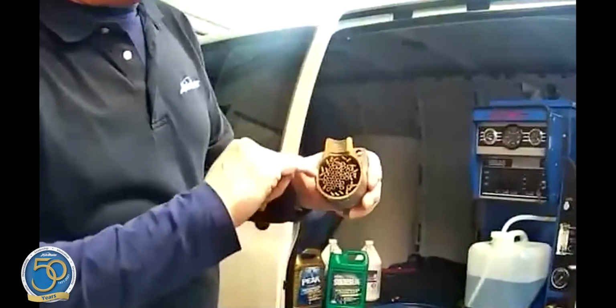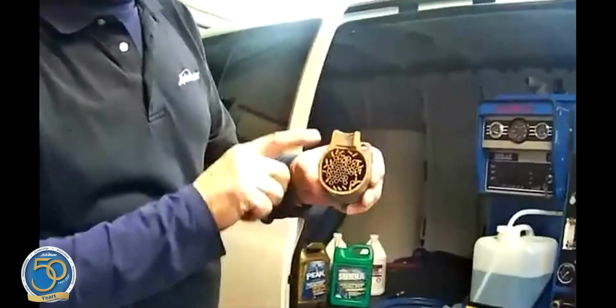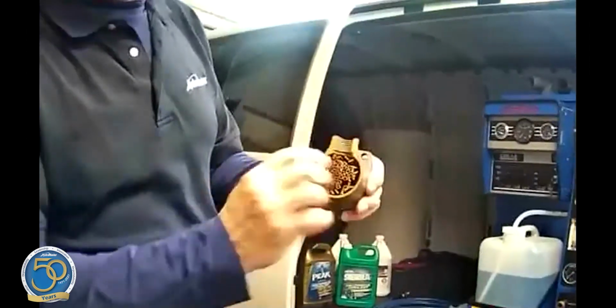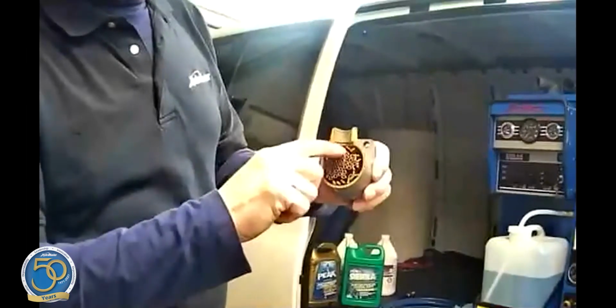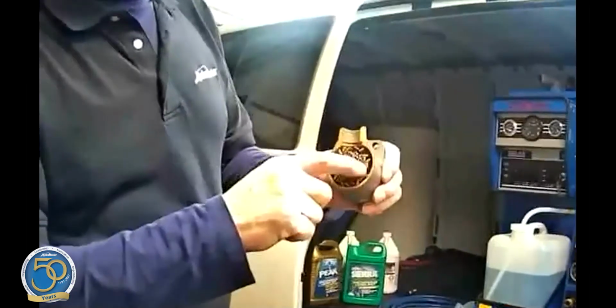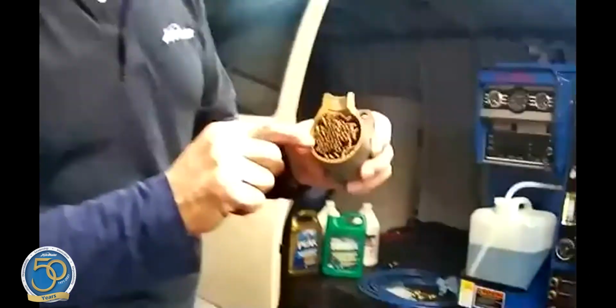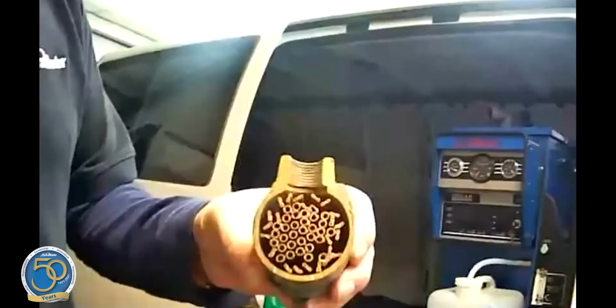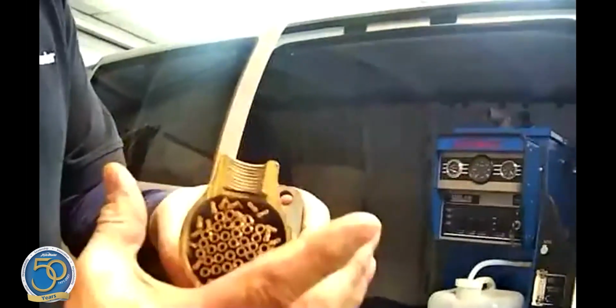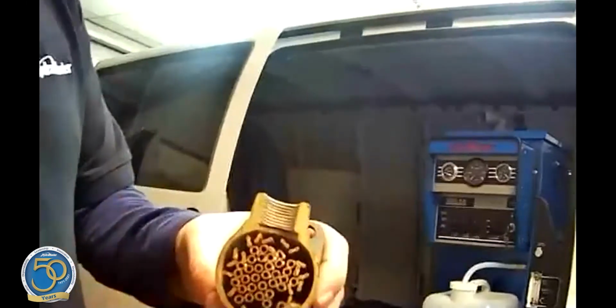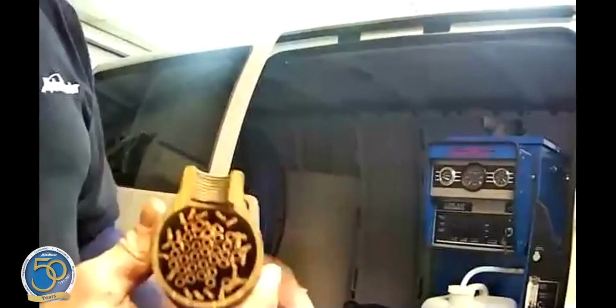See those tubes around the outer diameter of that heat exchanger? This is a tube and shell heat exchanger, with the outer shell and the inner tubes. You can see where the pressure from the ice has crushed those tubes. That's what happens, and it will expand the ends of the heat exchanger out, creating a situation where it's going to leak either internally or externally.